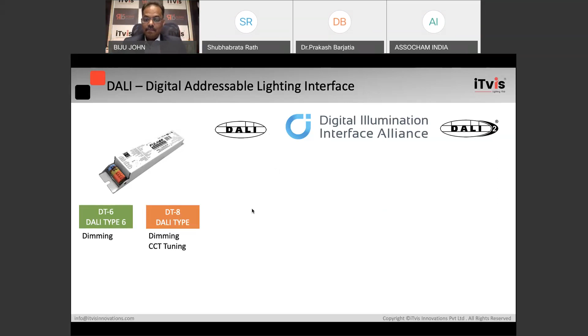But the change because of this standard edition is that DALI 2 now covers control gear, which is the ballast or driver, and it also covers the application controller, and even the sensors. You see the input device occupancy sensor, the input device light sensor, and the standard now covers the bus power supply and the bus also. So whatever you could see over here, the power supply is also covered in the DALI 2 standard. Control devices like push buttons and sensors, input device occupancy and light level, sometimes both of these are similar.